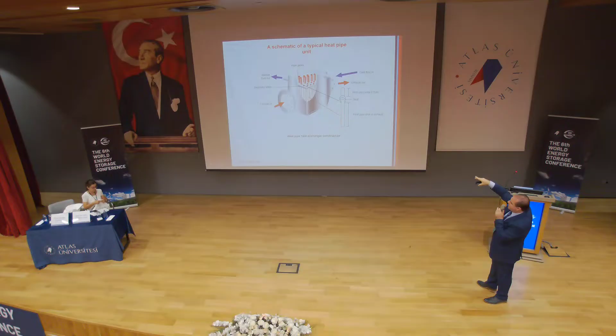Can we see examples? Let's have a look. A typical heat pipe heat exchanger is a box or cylinder, subject to the conditions inside. You can imagine it as a box. If you do a cut, it's a box separated by a separation plate. This plate separates the hot region from the cold region. In this scenario, exhaust flow goes in, the heat pipes absorb heat from the exhaust and deliver it to the heat sink fluid, which can be air, water, or anything.